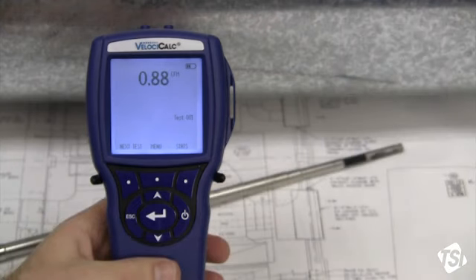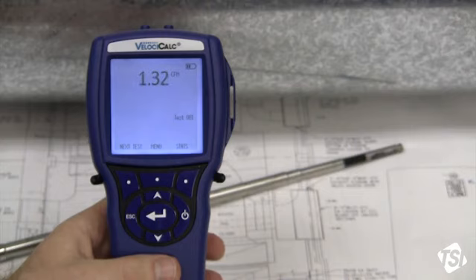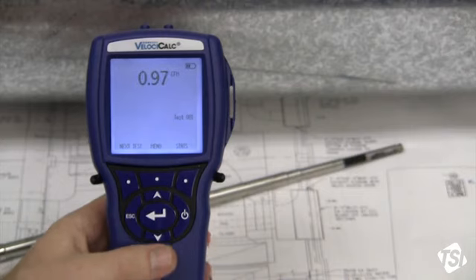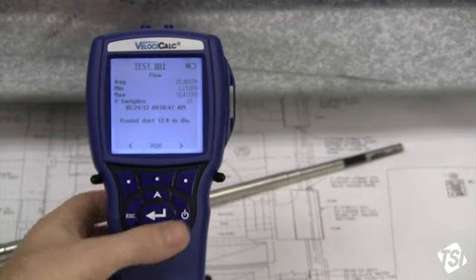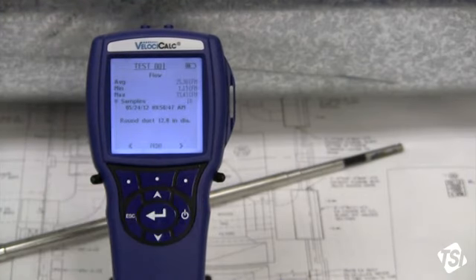After all the points have been measured across this section of the duct, I can review the statistics to find out what the overall average airflow rate was. I can press the right soft key to open up the statistics screen. I see that flow is the measurement I am displaying and the average is the airflow rate of the duct.